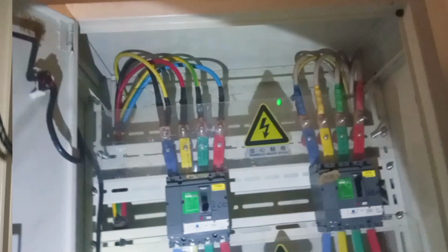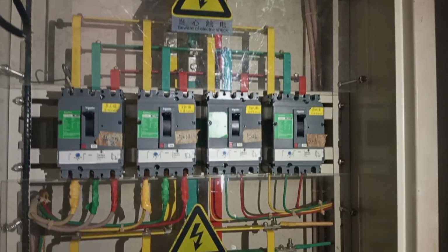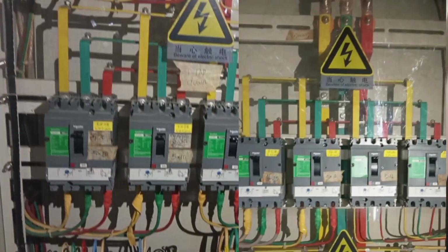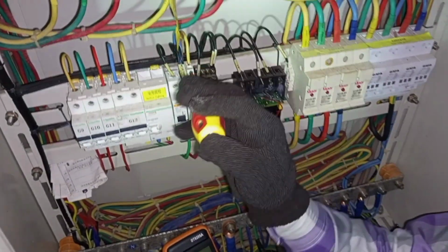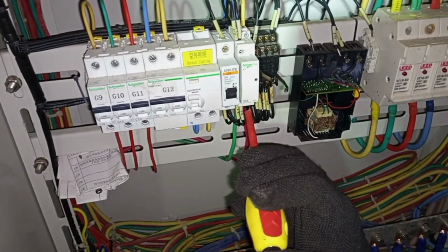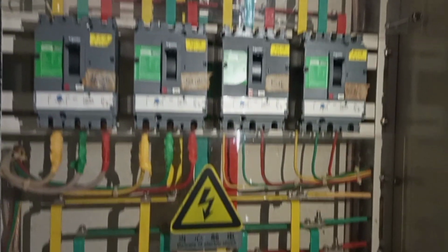So for this particular building, we have one panel that houses the arrangement of the changeover switch, and then we have another panel that houses MCCBs that distribute power to the various sections of the building. So the supply output from the changeover switch comes to this panel. This panel only contains MCCBs and a few devices for fire alarm and then outside lights. So in this particular building, there are 8 different sections, and each of these MCCBs supply power to a particular section of the building. So each of these MCCBs connect to a distribution board that houses circuit breakers to supply the different circuits in a particular section of the wiring.